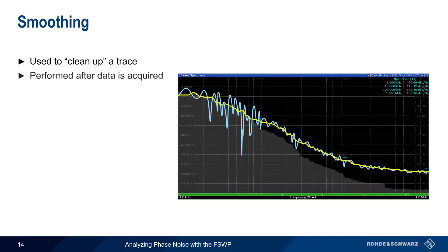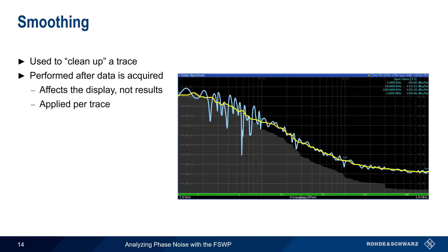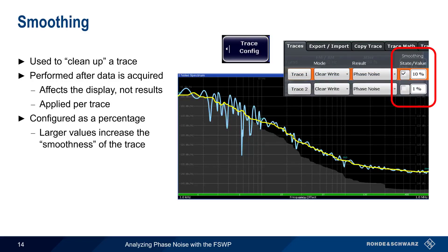Now let's spend a minute talking about ways of displaying phase noise results. Smoothing is used to clean up traces — here is the raw or unsmoothed trace, and here is the smoothed trace. Smoothing is performed after data is acquired; it affects the display, not the results. It is applied per trace, and it's possible to display both smoothed and unsmoothed traces simultaneously. Smoothing is configured under Trace Config and is specified as a percentage — larger values increase the smoothness of a trace.